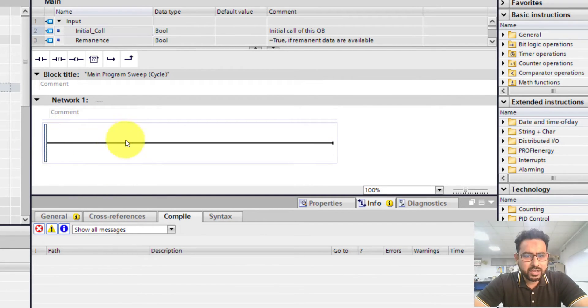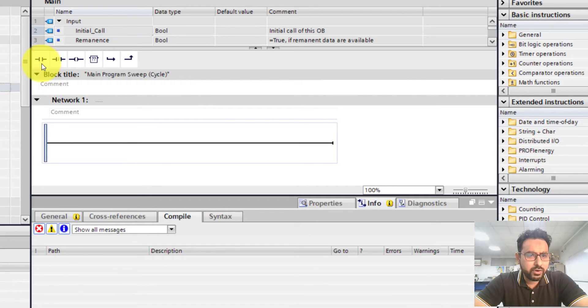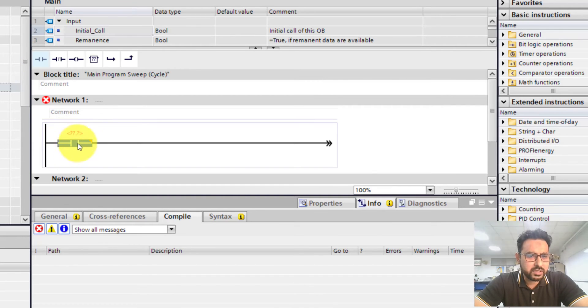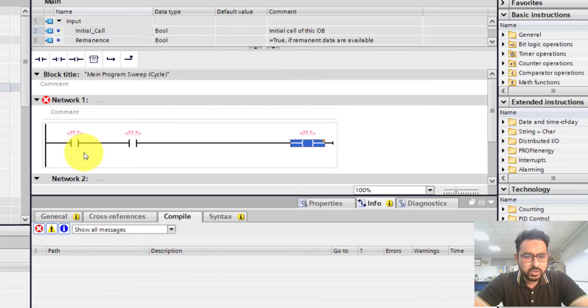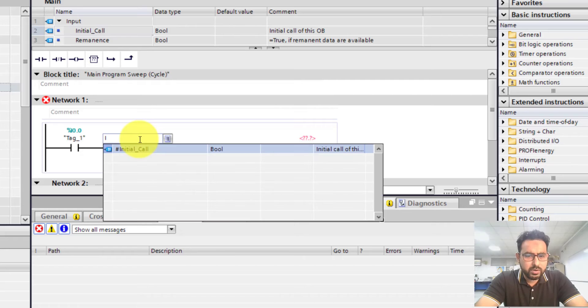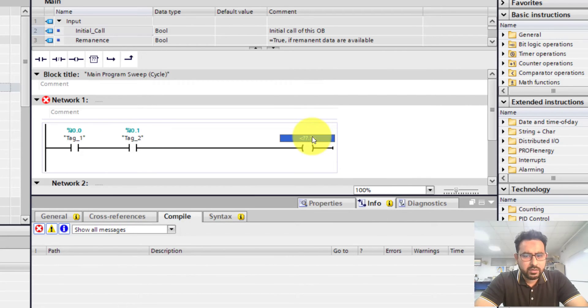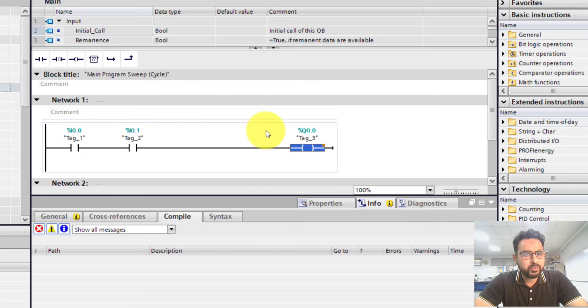Inside the Main block you have options to design your ladder diagram. Currently there is one rung present. I'm going to add a few blocks to mimic an AND gate using two inputs and an output. For the input I'll use a switch element — I need two in series and then an output. I'll assign addresses: first input at I0.0, second at I0.1, and output at Q0.0.